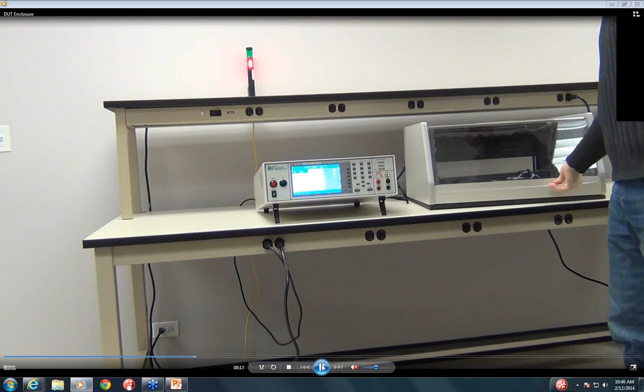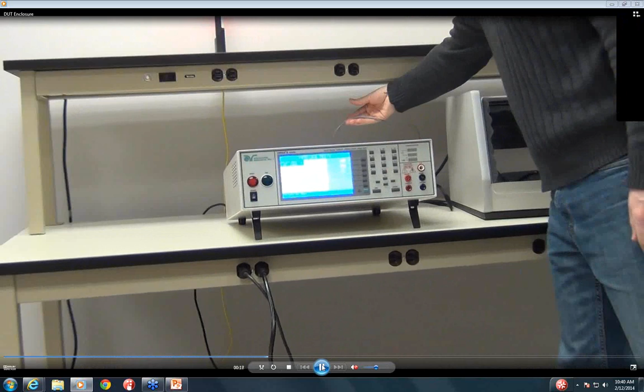So I'm going to shut the door, which is wired directly to my interlock on the back of the HiPot. I have those doors wired with a magnetic switch across pins 4 and 5 on my HiPot unit, and that ensures that if the door opens, the unit won't output voltage.